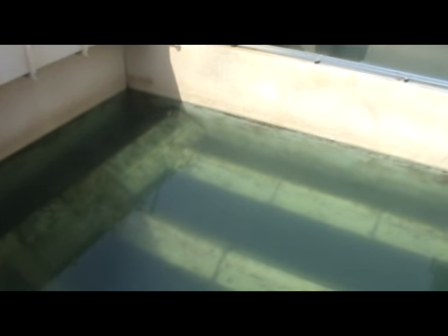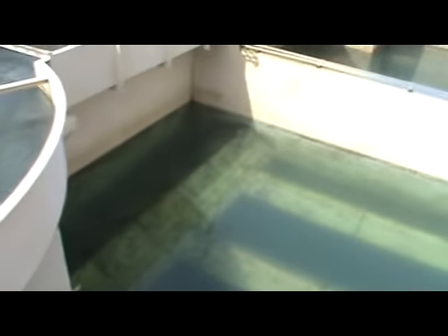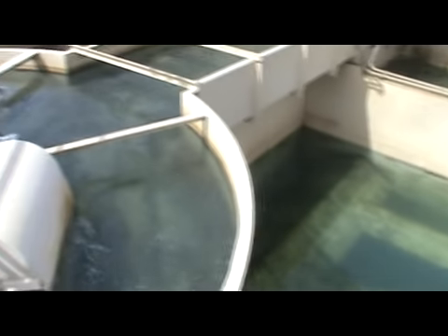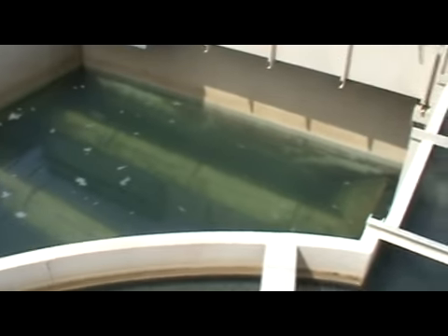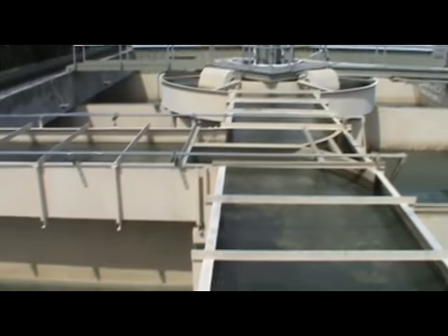Now, when I talk about adsorption, I'm not talking about the word with a B, to absorb, but adsorption with a D. That's the collection of a solid, liquid, or gas on the surface or interface zone of another material. So basically they collect those things and catch them in the filter beds. Now there's going to come a time when a filter has caught as much as it's going to catch. That's when you know it's time to backwash that filter, time to clean that filter out.